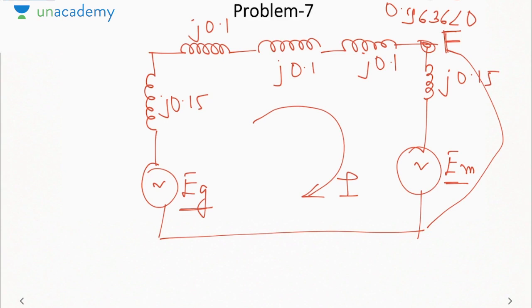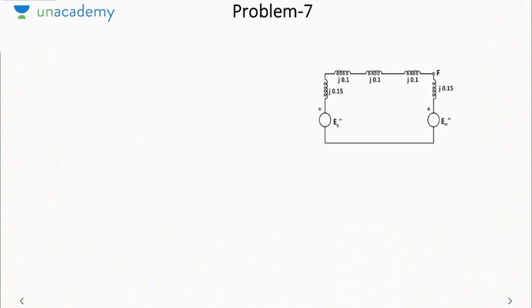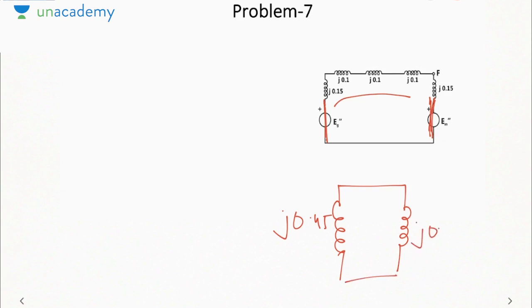But the other way around, in the next step it asked us to remove all the voltage sources and we will get a passive Thevenin network. So you will remove this voltage source, short circuit this. The network that will remain is these four in series. This will be 0.45, and this will be in parallel with J0.15. This will be the network that will remain. This is my fault point.